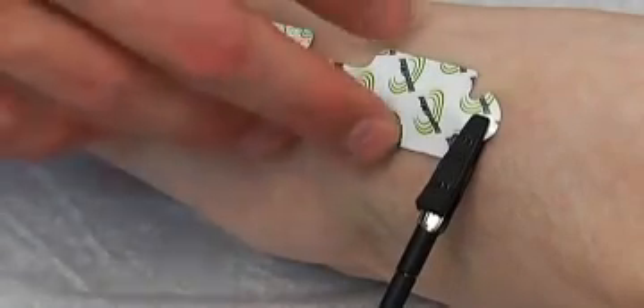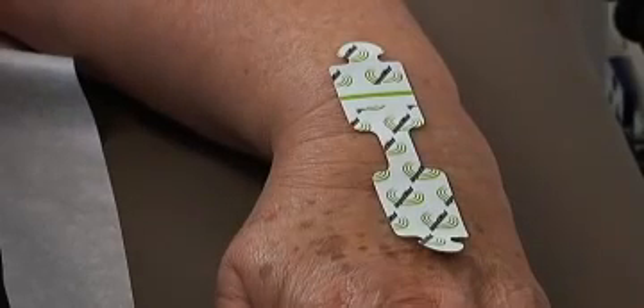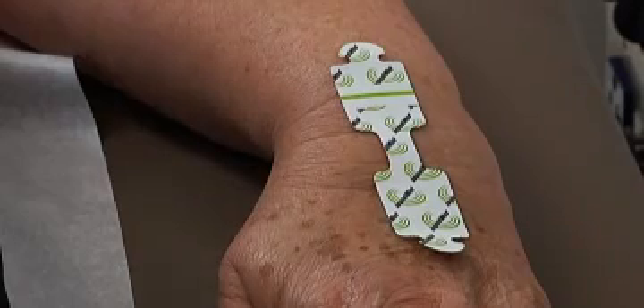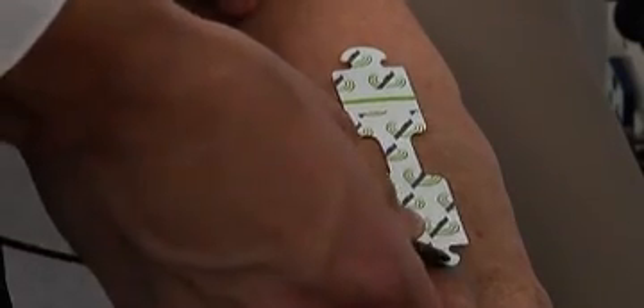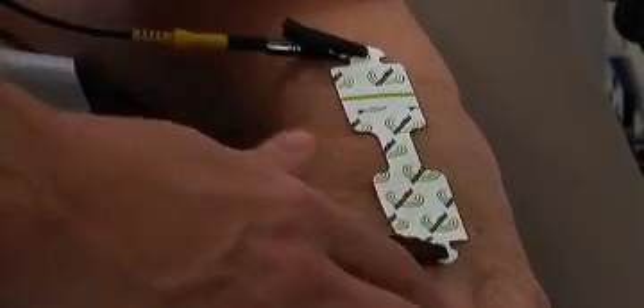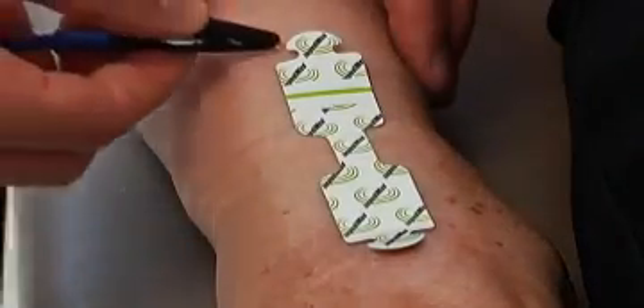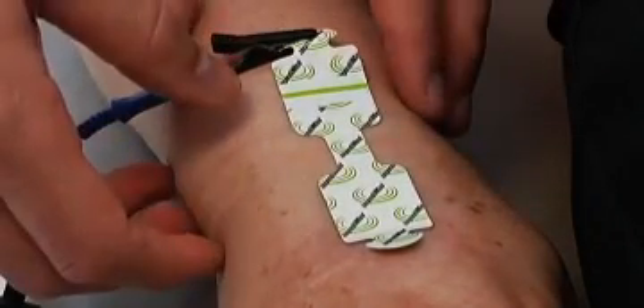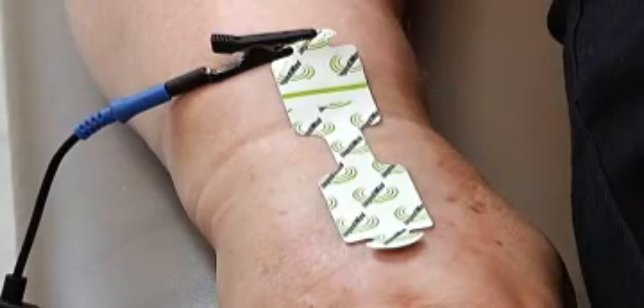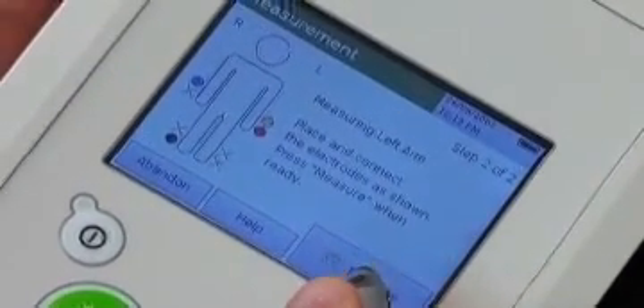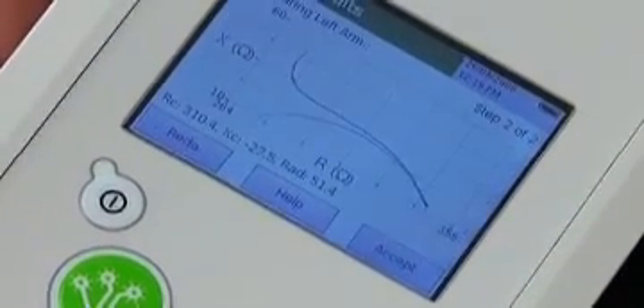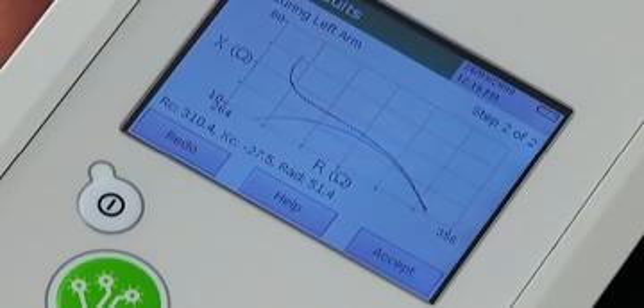Following the measurement guide on the on-screen prompt, the black lead remains in place. The red lead is moved to the distal end of the dual tab electrode on the left hand. The yellow lead is moved to the wrist of the left hand, and the blue lead is moved to the wrist of the right hand. Double-check your placement and select Measure. The device will take an impedance measurement of the left arm from the shoulder to the wrist.